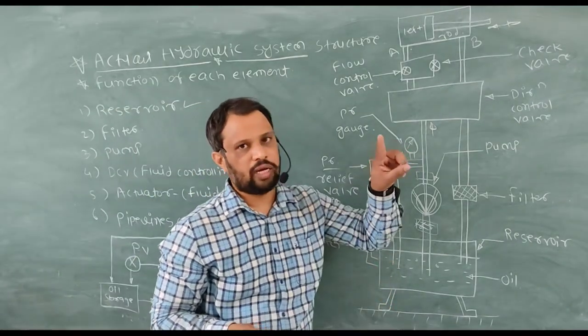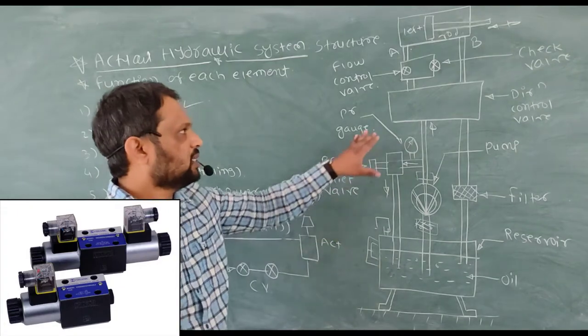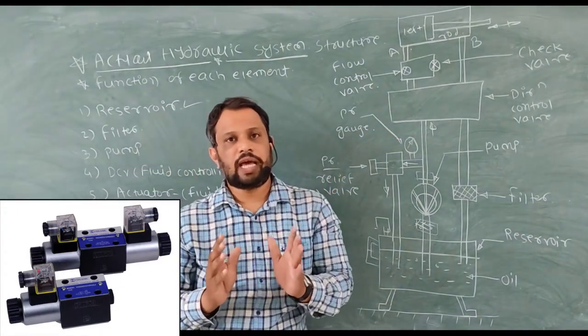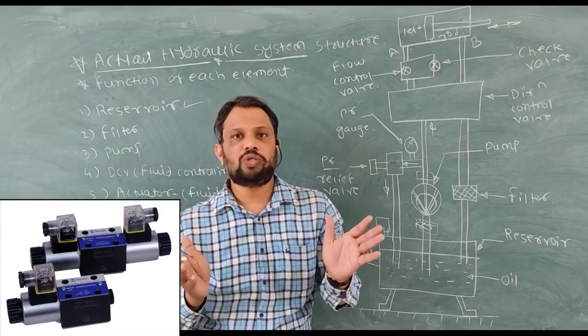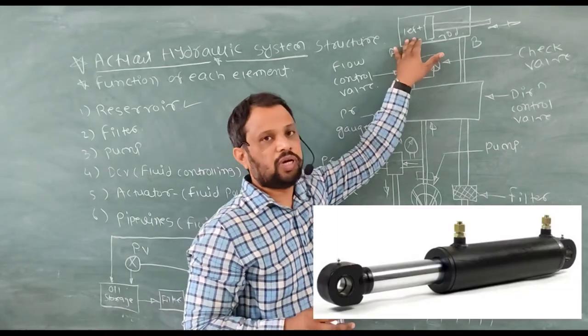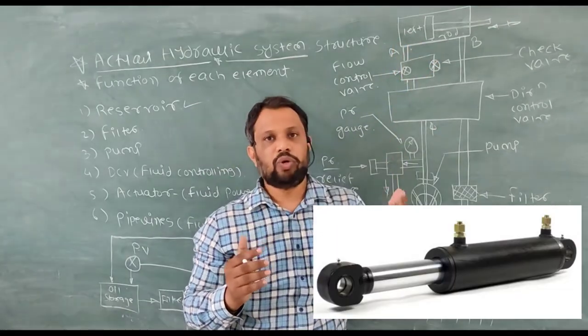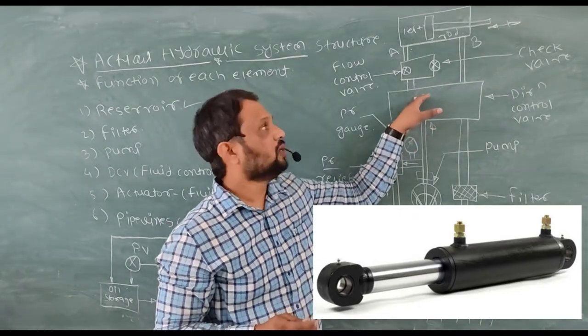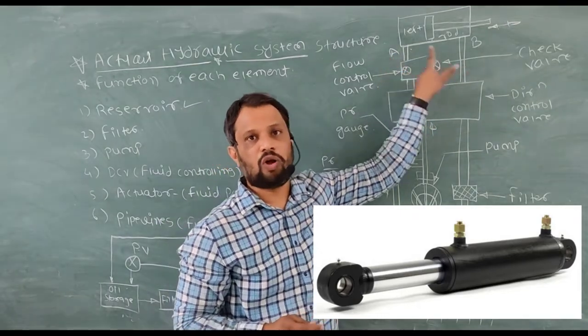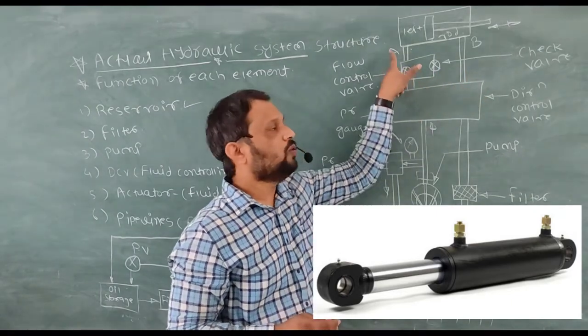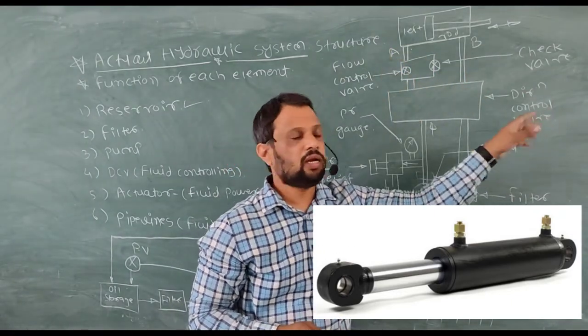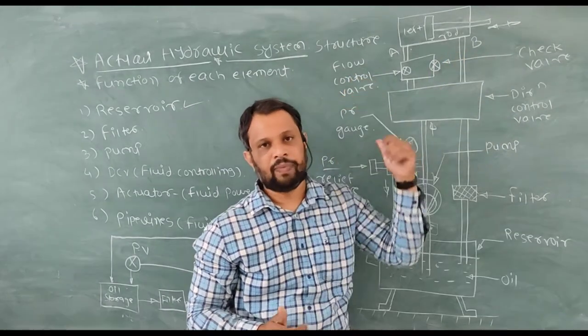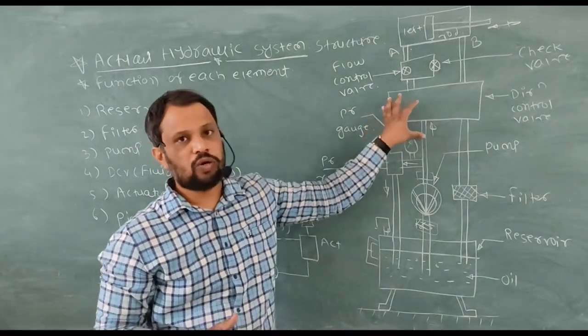The pressure gauge shows your pressure reading. After that, the direction control valve acts as a traffic signal — it decides where to send the oil. The actuator, also called a cylinder, receives oil based on the direction control valve's decision. The direction control valve decides whether oil should be sent to the A side or B side. If oil is sent to the A side, the piston shifts to the right; if oil is sent to the B side, the piston moves towards the left. This is your controlling element.